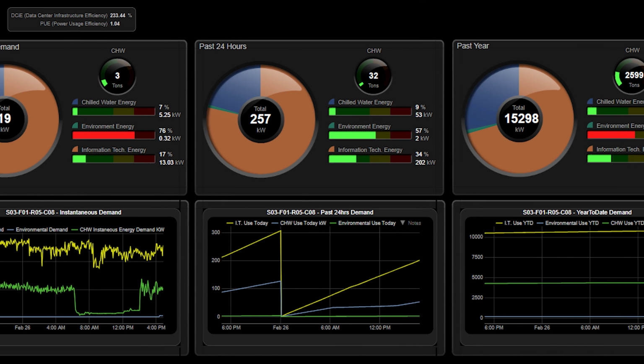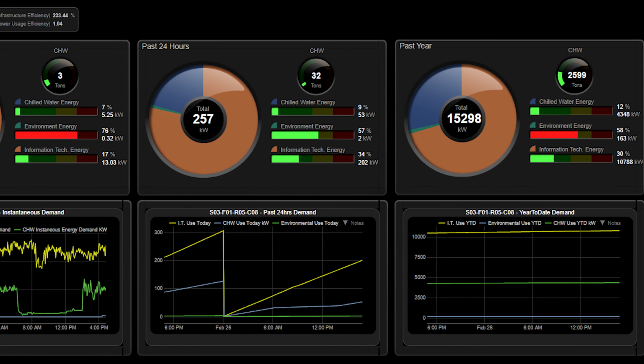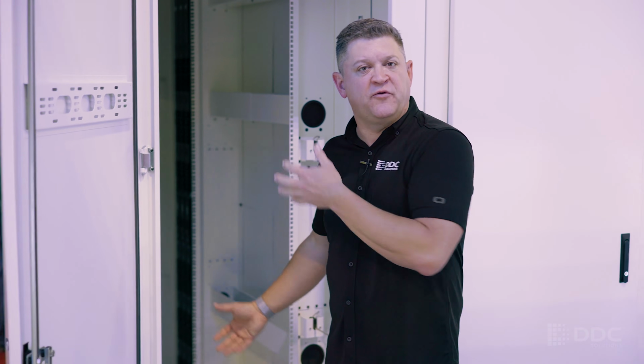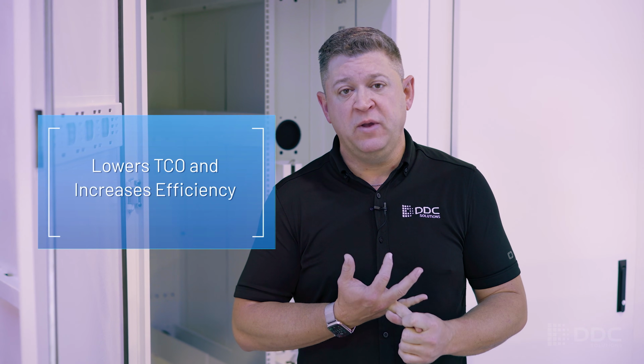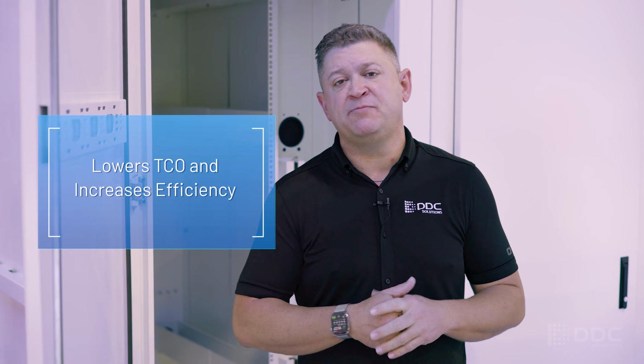We use that data to control temperature and air pressure, ensuring ideal environmental conditions for server workloads. At the facility level, we concatenate all that data to see the true demand for the facility, feeding it back into the building management system to ensure we're not producing or utilizing energy anywhere it isn't needed, based on real-time load dynamics of the cabinet. This is how DDC helps improve operational costs, lowers PUEs, and delivers total cost of ownership improvements for any data center operator today.